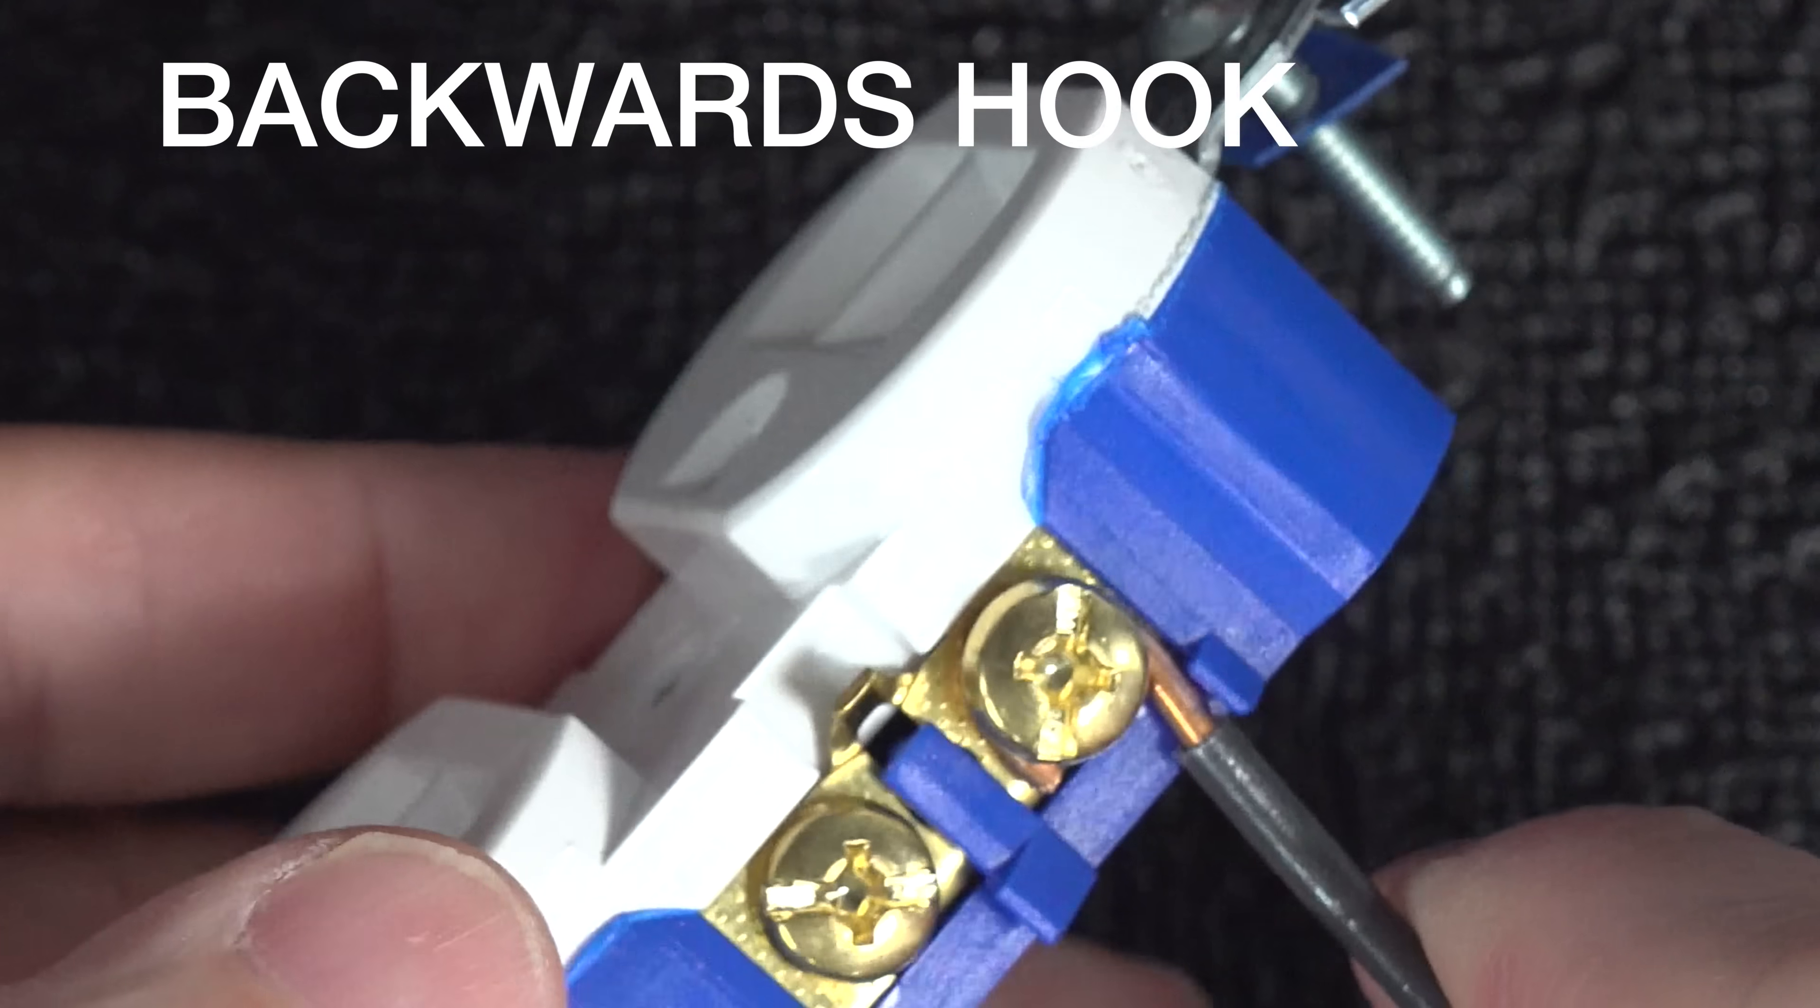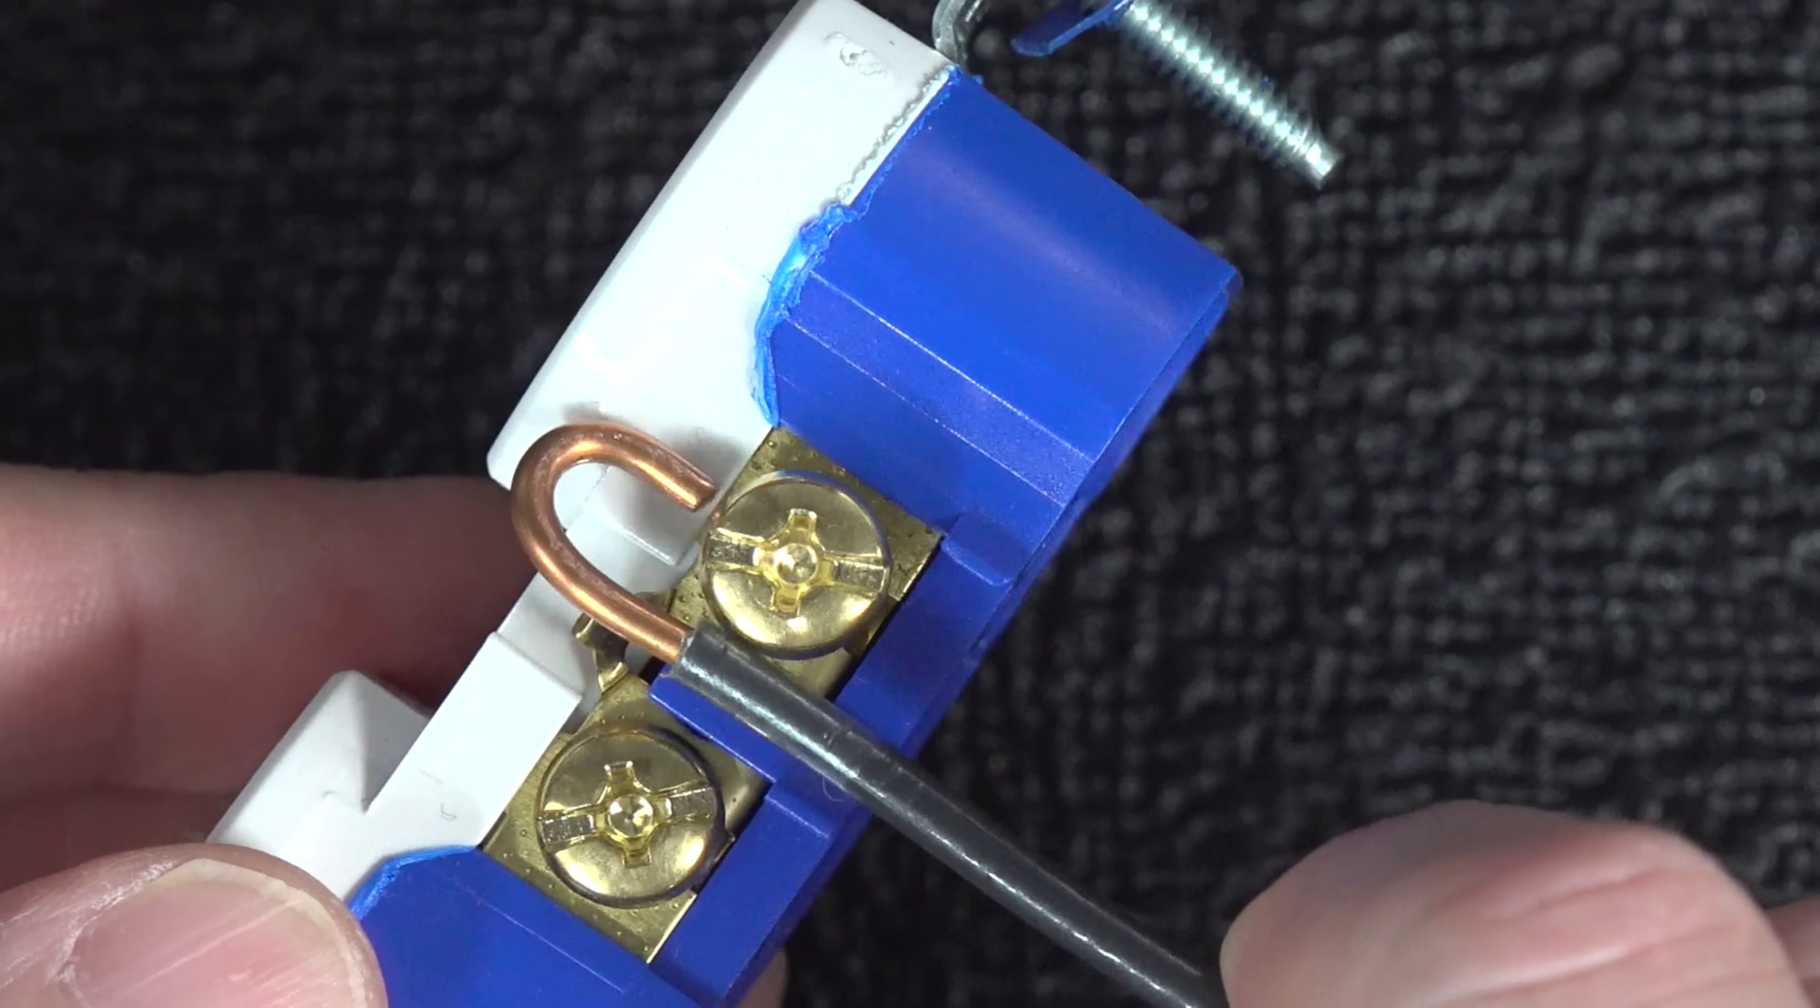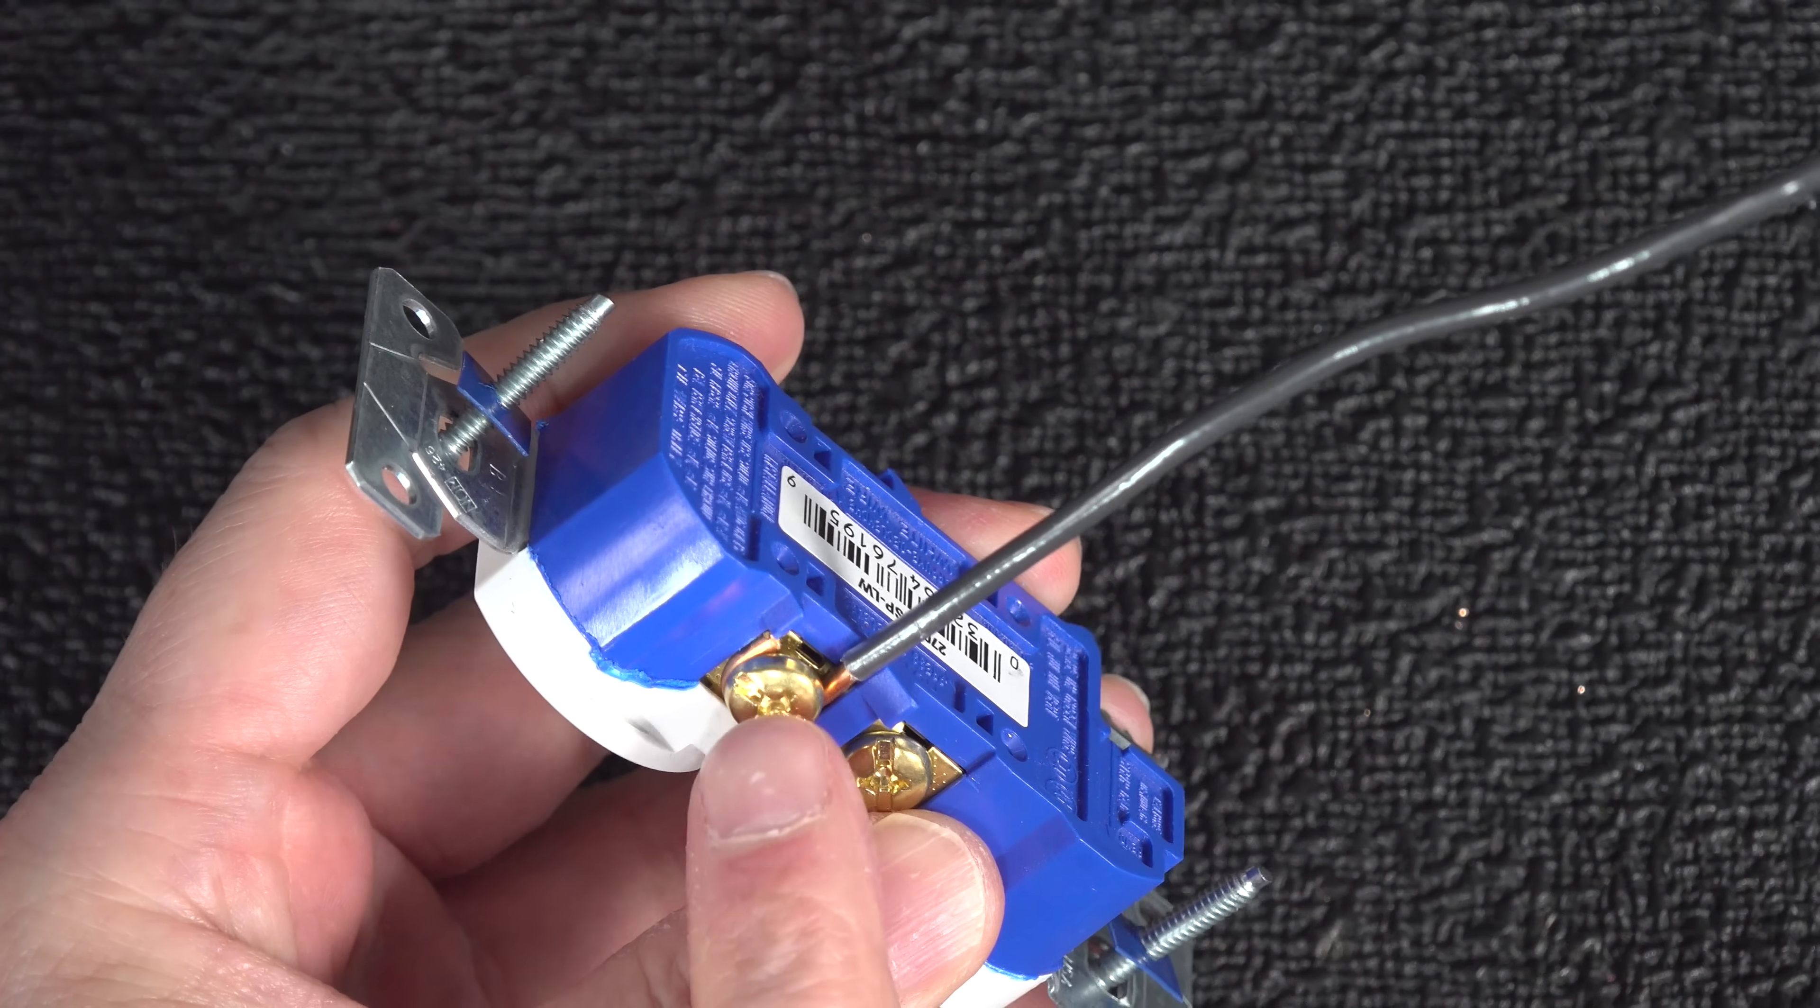Now it matters which direction that hook is facing because that screw tightens down screwing clockwise and you want the end of the hook to be facing to the right. And now as I tighten that screw down, it's actually going to pull the wire in a little bit tighter and that's going to give you a secure connection. If I have that hook facing to the left, as I screw it down, it's actually going to force the wire out and that can make it slip off.